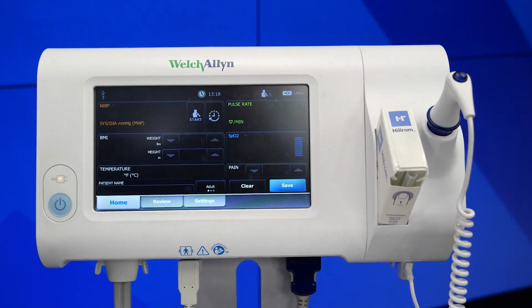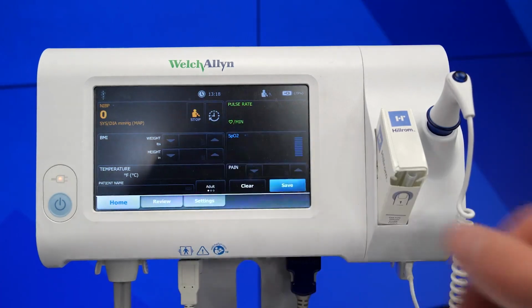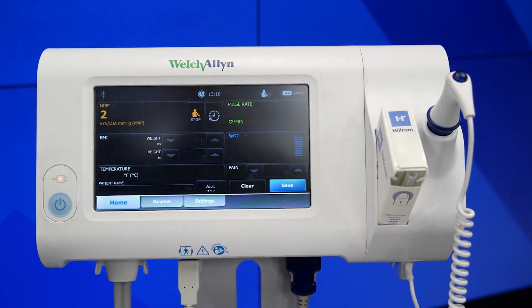Once the patient is fully situated and the cuff is applied, press the Start button on the NIBP tile to initiate a singular reading. The cuff will inflate with the Sure BP algorithm and capture a measurement on inflation. If the device detects motion or artifact, it may default to step deflation in an effort to obtain a reading.